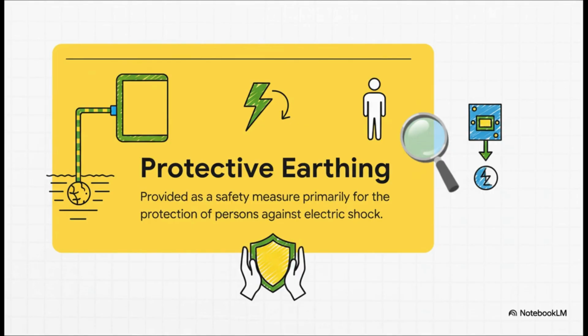That's its one and only job. It gives that fault current such an easy path back that the surge of electricity becomes massive enough to instantly trip the circuit breaker, shutting off the power long before anyone can get hurt.